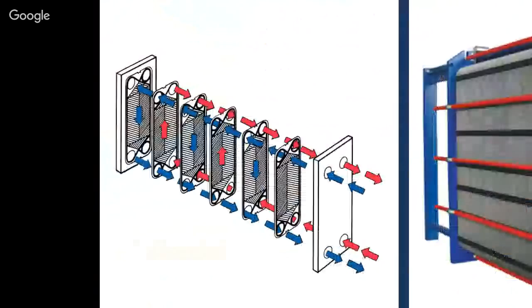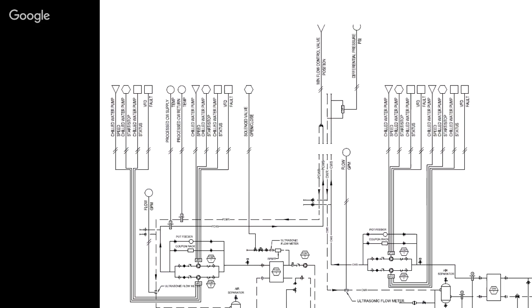Because for me to size this pump, I need to know flow rate and I need to know pressure drop. If they say, well, I just need 80 psi, well, that's what they get from the tap water. We need to know incoming and exiting pressure so that we can actually size this pump. What typically happens, if they don't know it, they give us the wrong information or we guess, and then it's wrong, then the equipment doesn't work or it can't cool to its specs. So whatever this group can do to help that.